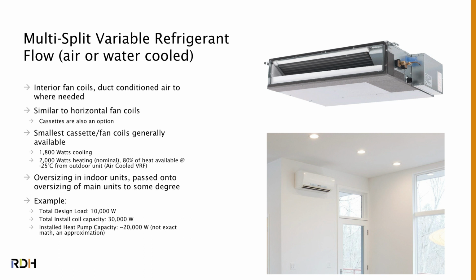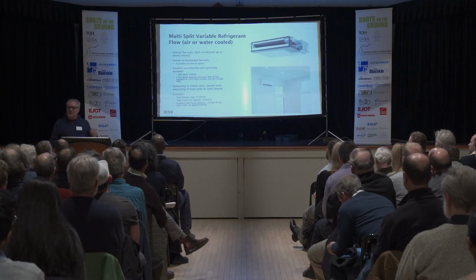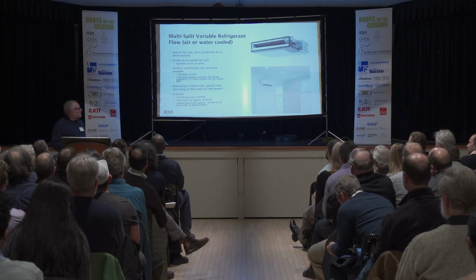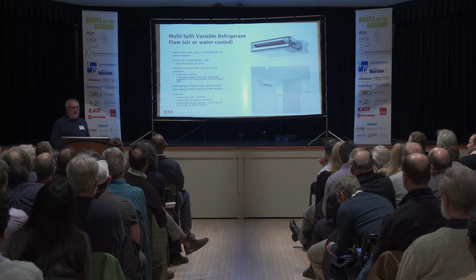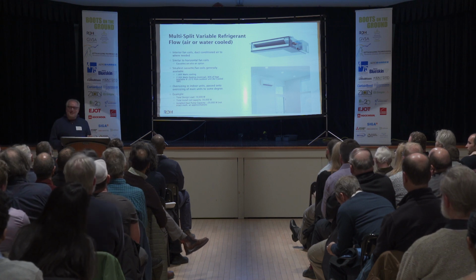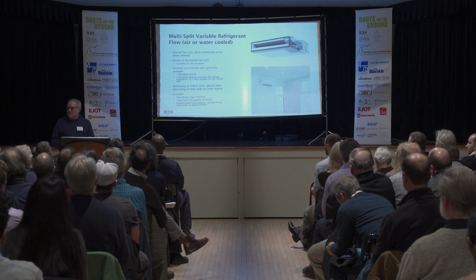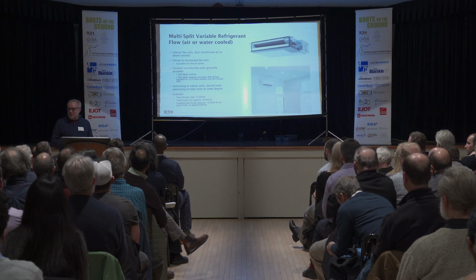The smallest ones I can find bottom out at 1,800 watts cooling, 2,000 watts heating. Again, they're almost 2 to 3 times the size we need per suite. And one of the challenges with VRF is you can't necessarily buy the smaller central heat pump that just matches your load.